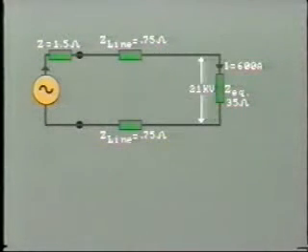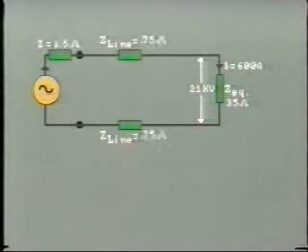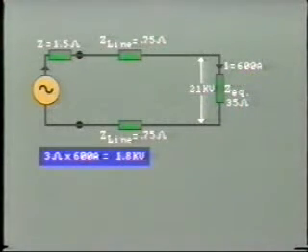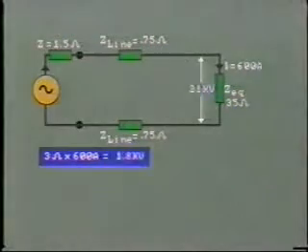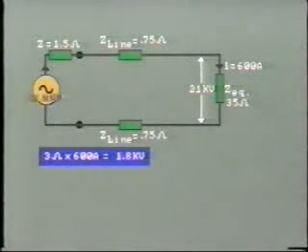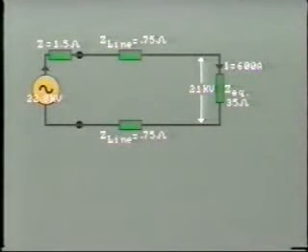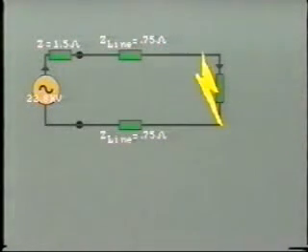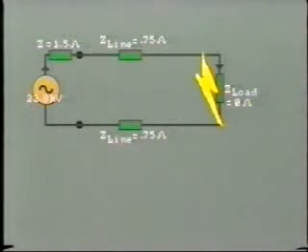As extra load is added the voltage at the generator must be increased slightly in order to maintain 21 kV at the load. Let's work out the voltage drop between the load and the source. Total impedance comes to 3 ohms. Multiplying this by 600 amps gives us a voltage drop of 1800 volts, that is 1.8 kV. So the internal voltage at the generator is 22.8 kV. Now let's see what happens if we have a direct short circuit at the far end of the line right across the load. The load impedance now falls to zero.